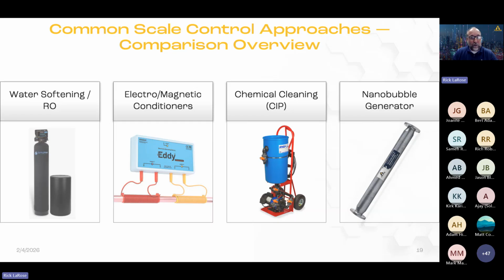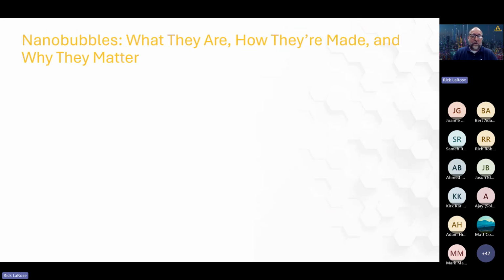The nanobubbles will remove scale over time, and we've seen that happen. The timing varies—we don't know how thick the scale is in your system. I've seen it take anywhere from days to weeks to months, but it will remove legacy deposits. The real power, though, is in its ability to inhibit new scale. So we position this as a maintenance and conditioning strategy rather than an immediate scale removal strategy.